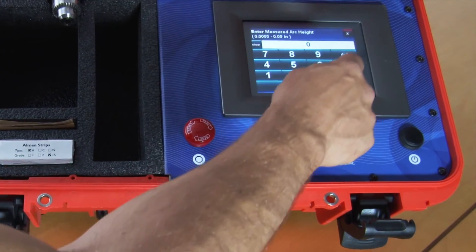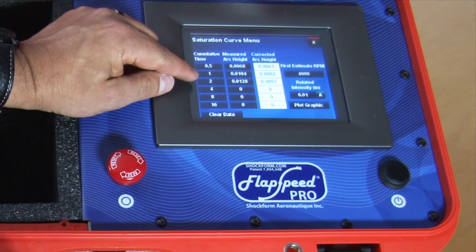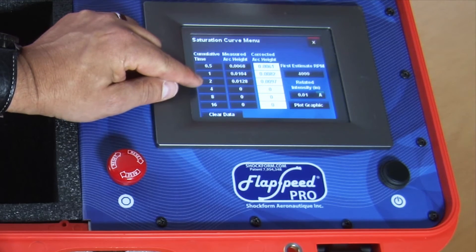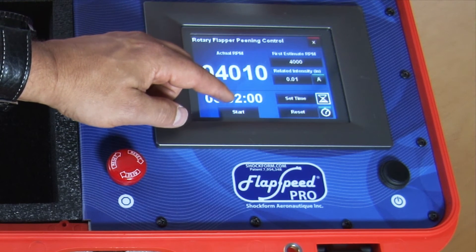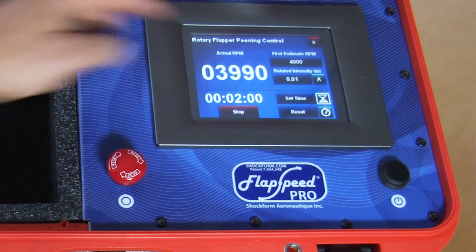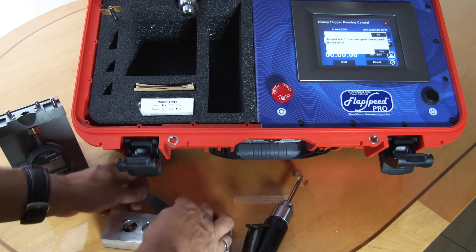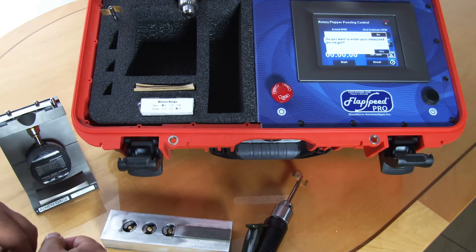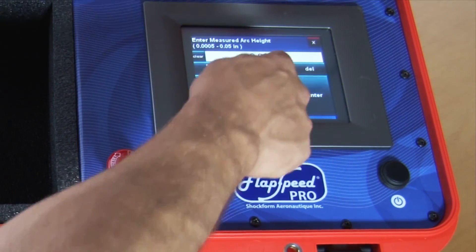We enter 0.0128. We need a minimum of four points for the saturation curve. We've done a cumulative up to two minutes, so we need an extra two minutes to reach four minutes. Once we reach steady state we press the start button. The timer reaches zero, we take the arc height measurement — 0.0146 — and enter that into the system.